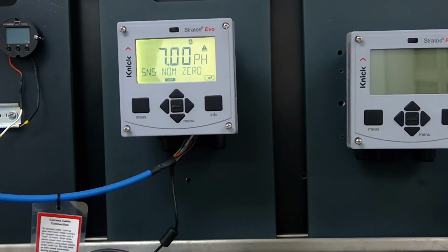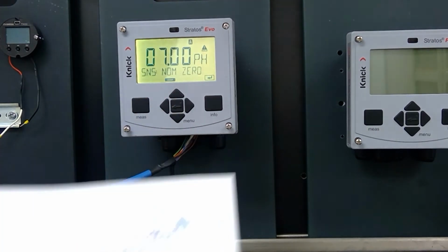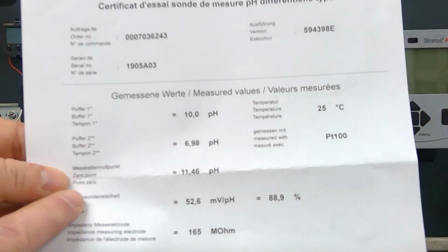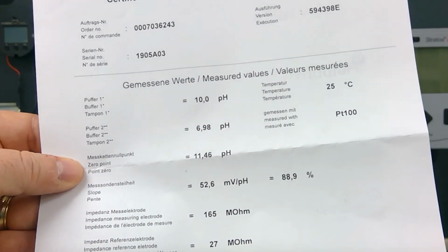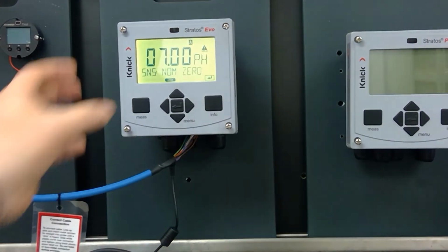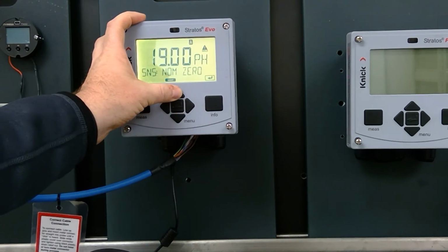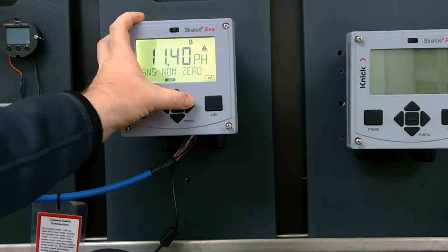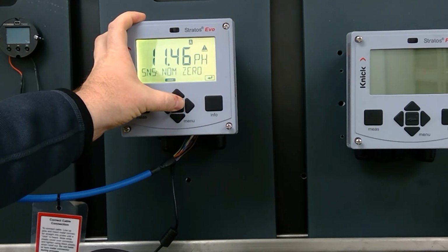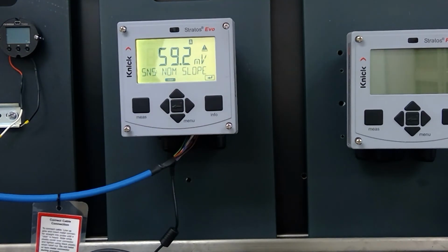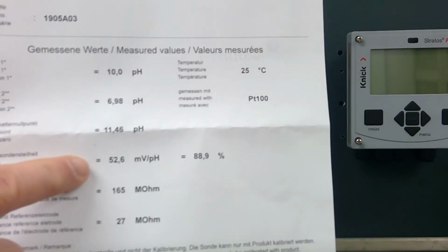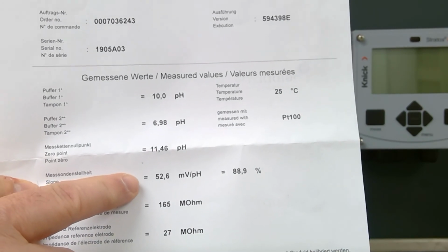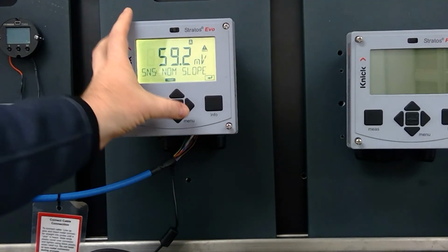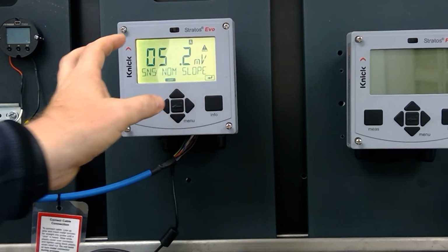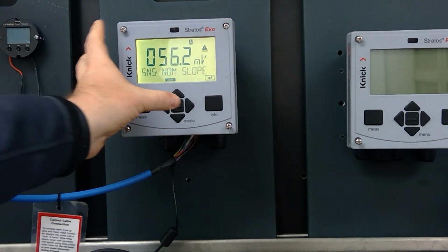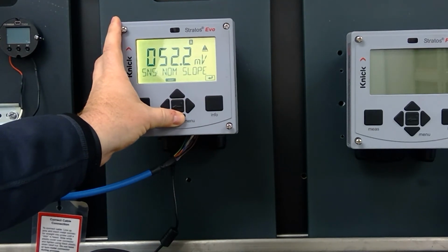nominal 0. So this is an important piece of information. What you need is on your test certificate, it's going to say 0 point. In this case, it's 11.46. That's unique to this electrode. 11.46. Okay, and then we also need nominal slope. In this case, it's 52.6 millivolts is the value we're going to use. 52.6. So you want to make sure you get this right.